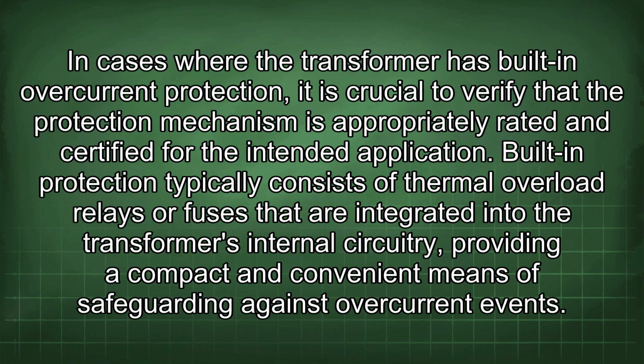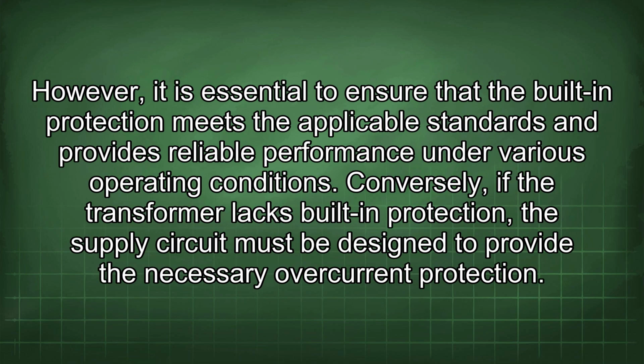In cases where the transformer has built-in overcurrent protection, it is crucial to verify that the protection mechanism is appropriately rated and certified for the intended application. Built-in protection typically consists of thermal overload relays or fuses that are integrated into the transformer's internal circuitry, providing a compact and convenient means of safeguarding against overcurrent events. However, it is essential to ensure that the built-in protection meets the applicable standards and provides reliable performance under various operating conditions.